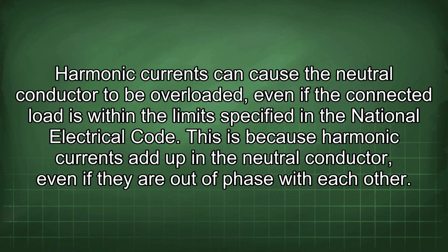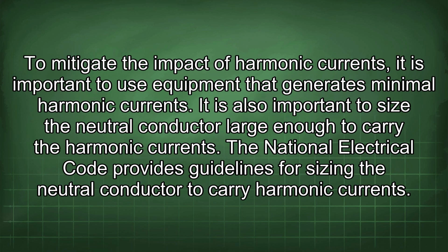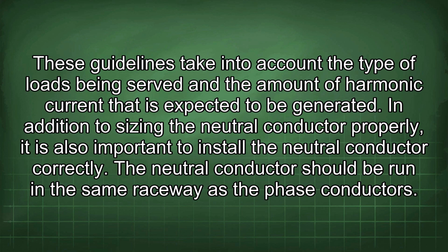This is because harmonic currents add up in the neutral conductor, even if they are out of phase with each other. To mitigate the impact of harmonic currents, it is important to use equipment that generates minimal harmonic currents. It is also important to size the neutral conductor large enough to carry the harmonic currents. The National Electrical Code provides guidelines for sizing the neutral conductor to carry harmonic currents. These guidelines take into account the type of loads being served and the amount of harmonic current that is expected to be generated.